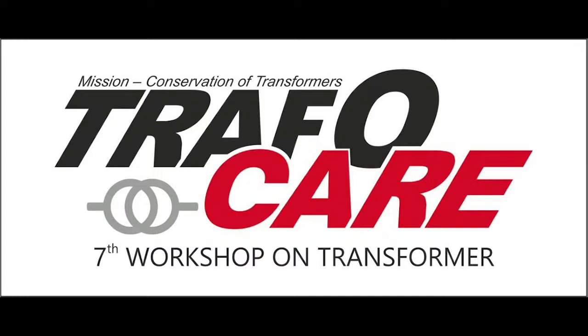Second thing is about tightness. We know that upper bolted constructions are regularly used in India, but I have seen that some leading European and developed countries are adopting welded flanges. So they straight away eliminate the possibility of oil leakages coming out of the curb area. This is also indirectly a design area, because the tightness, the type of design of the gasket, the groove design - all those things also relate to mechanical design.